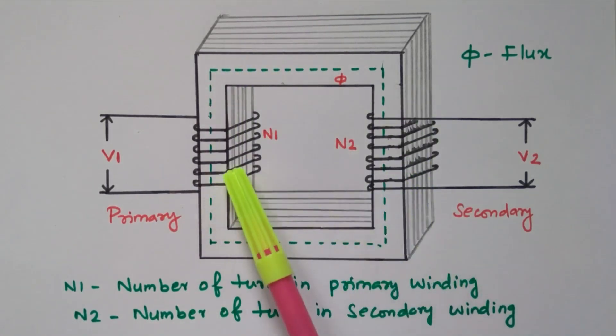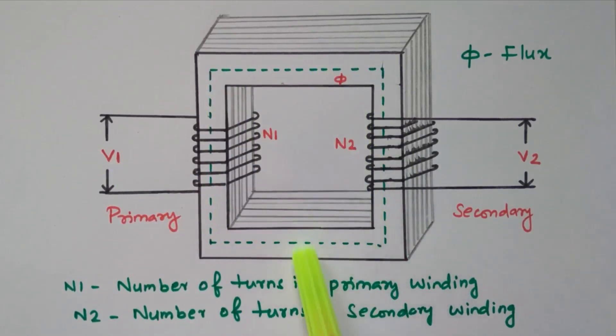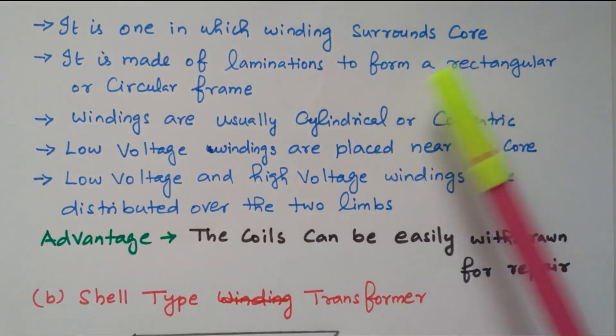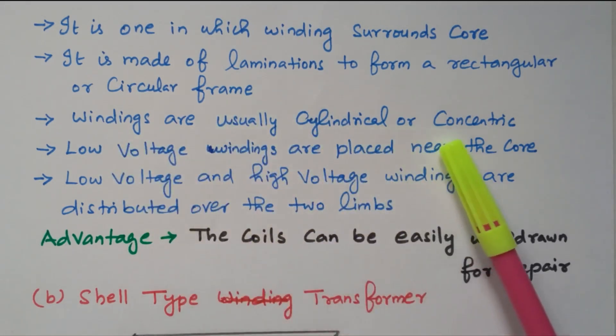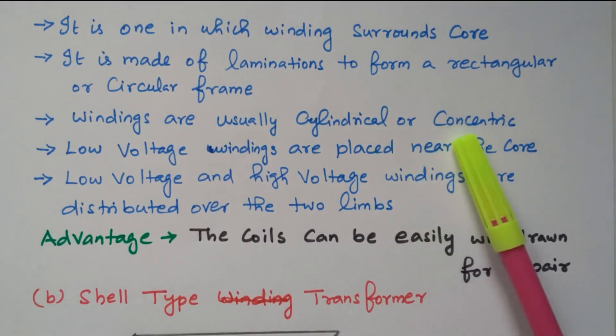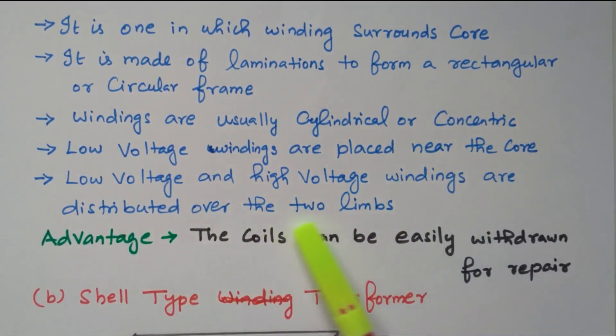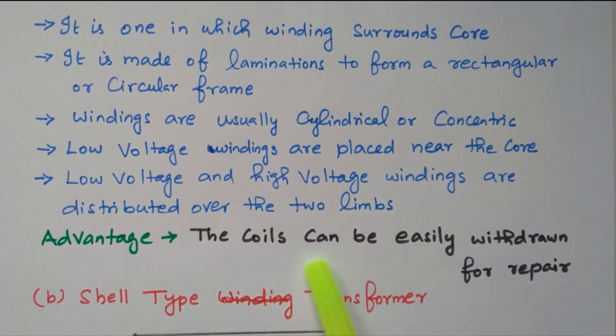In the core type, the core is available and over the core the coils are placed — so it is called a winding surrounding the core. It is made of laminations to form a rectangular or circular frame, and the windings are usually cylindrical or concentric type. Low voltage windings are placed near the core, and low voltage and high voltage windings are distributed over the two limbs. The main advantage is the coil can be easily withdrawn for repair, since we can remove the core easily to access the coil.